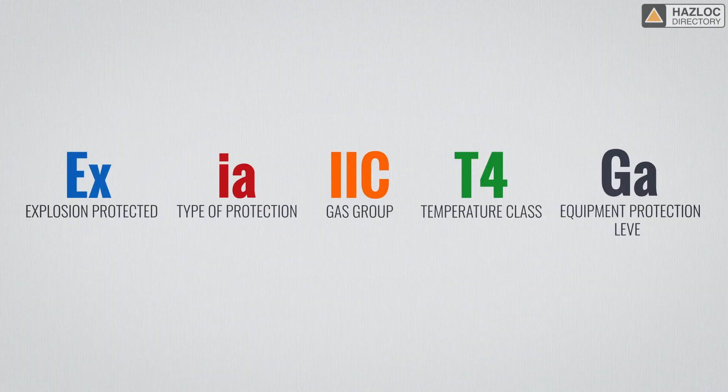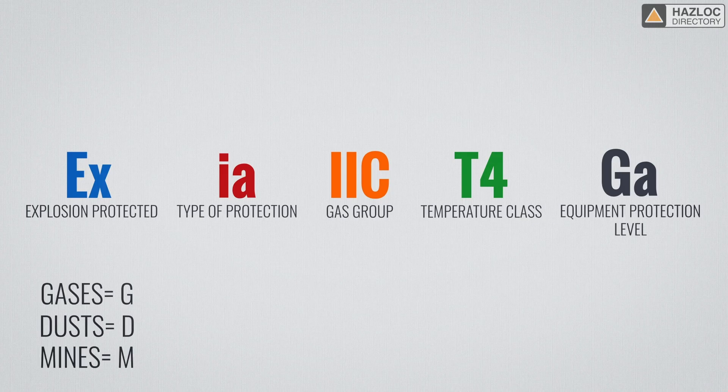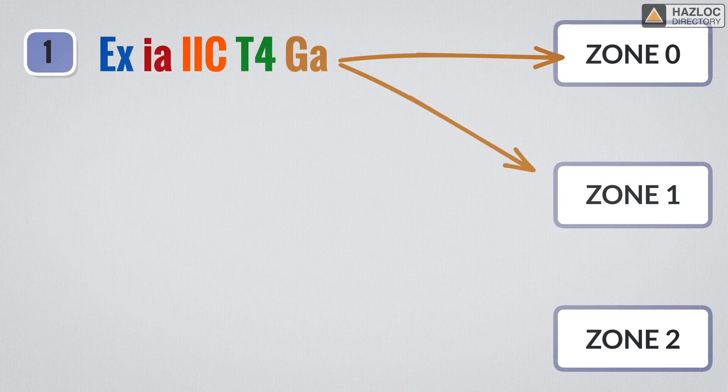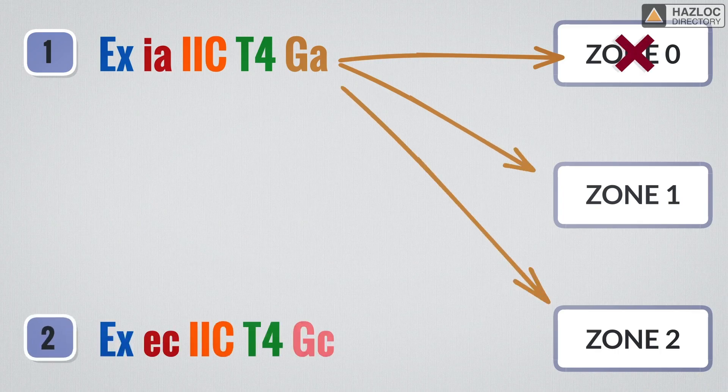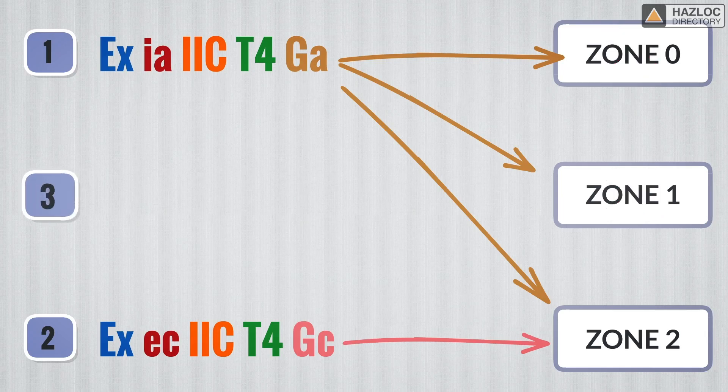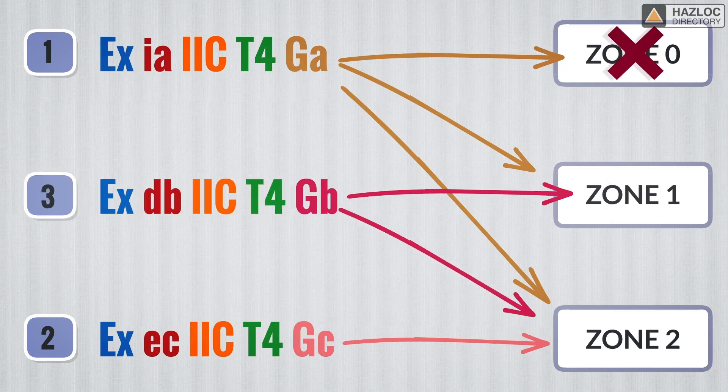The final part of the marking adds detail to the level of protection: EPL. The assigned EPL indicates the likelihood that the equipment can become a source of ignition. The EPL of gases is always shown as G. EPL of dusts are shown as D. EPL of mines is shown as M. Our example indicates G, meaning that gases are involved. Because zones, by definition, indicate the nature of the hazard, there is a correlation between the zone and the EPL. An EPL of GA refers to zone 0. GB dictates that the product must be installed in zone 1, and GC is for zone 2. Note that a product with an EPL of GA can be installed in zone 0 as well as zones 1 and 2. But a product with an EPL of GC cannot be installed in zone 1 or zone 0 due to the hazards involved. Similarly, a product marked with an EPL of GB is not allowed to be installed in zone 0 but is safe to be installed in zones 1 and 2.